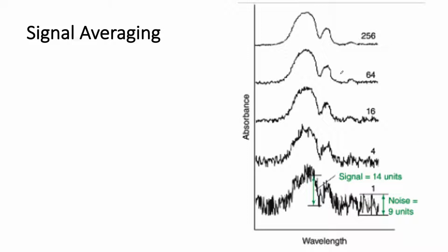Okay, so far, now you have a trade-off when you're determining signal to noise: which cuvette you're going to use to make sure it has as much transmission, what light source to use, right? Because there can be a choice of light sources, some of them having more light at certain wavelength ranges, which detector to use, which grating to use, what to set the slits at, right? And how fast or how long to average, right? So you can either scan or make multiple scans or just scan slowly.